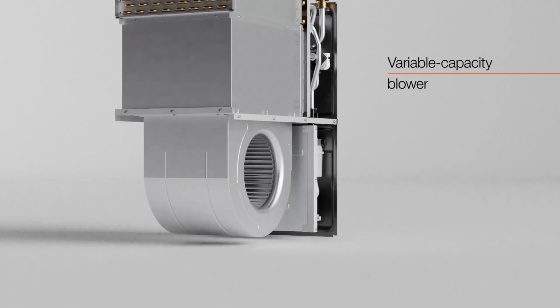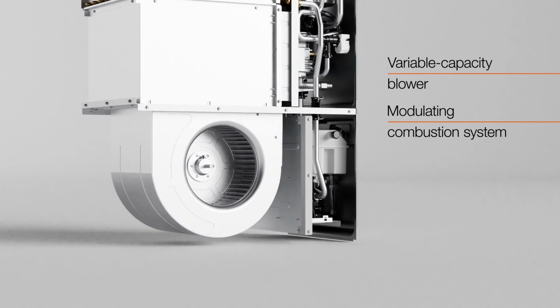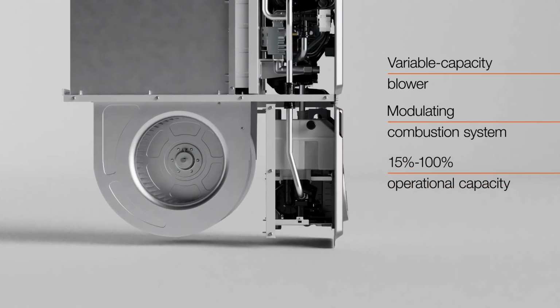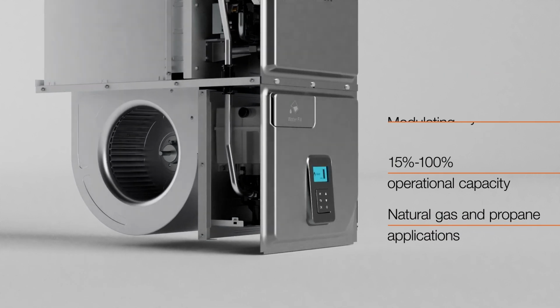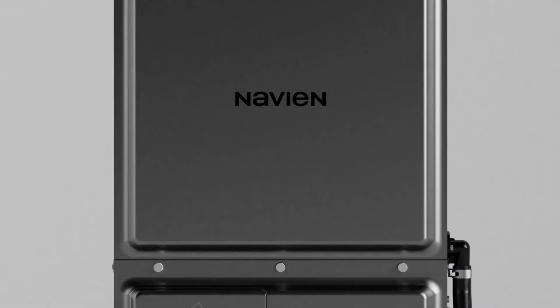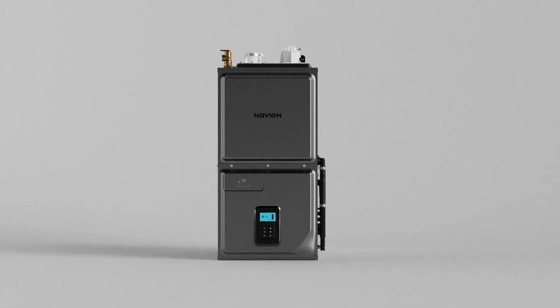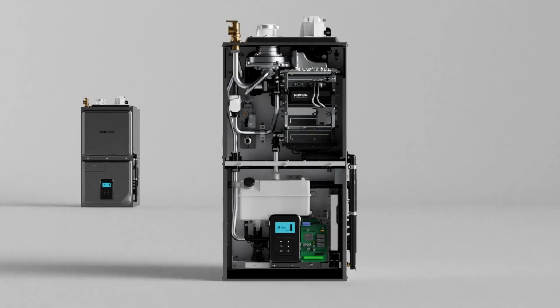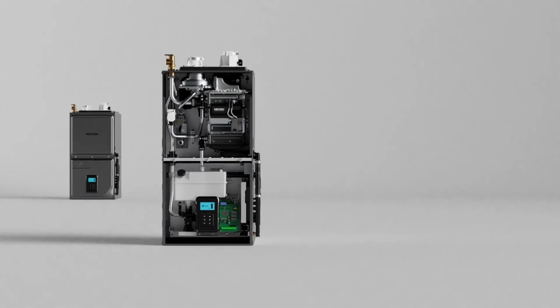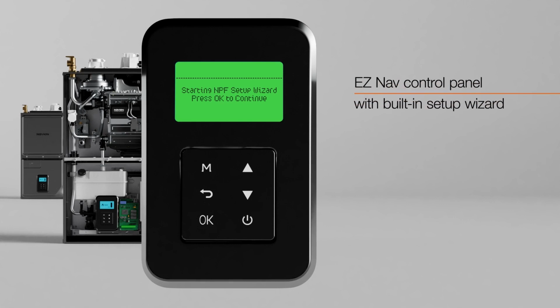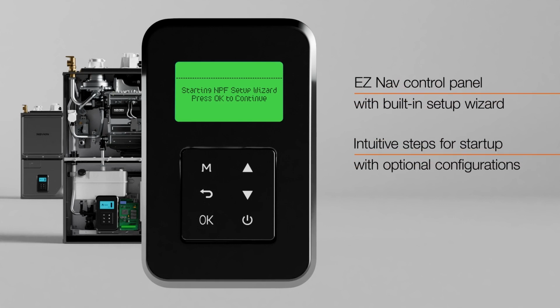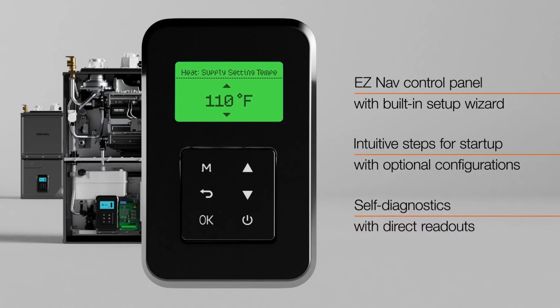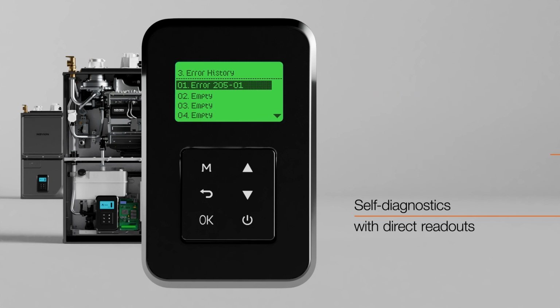Featuring a variable capacity blower and modulating combustion system that allows it to operate from 15% to 100% capacity for both natural gas and propane applications. Variable capacity heating operation continuously monitors air temperatures and will automatically adjust burner operation and airflow to maximize comfort and efficiency. The EasyNav control panel with built-in setup wizard provides simple, intuitive steps for startup, optional configurations, and diagnostics. The self-diagnostics provide a direct readout in clear text, indicating any diagnostic alerts or reminders saved in non-volatile memory.